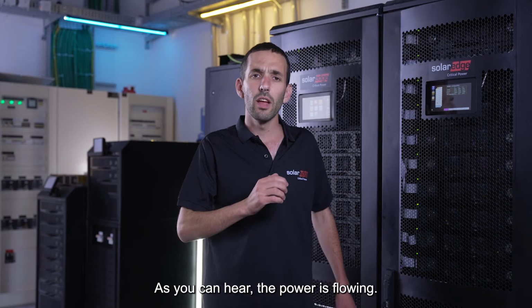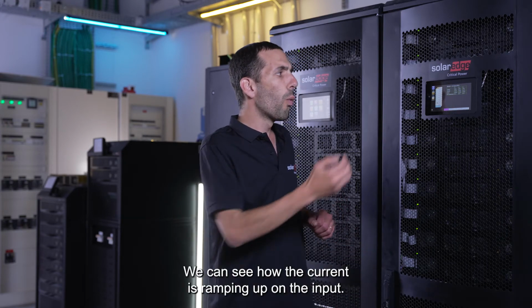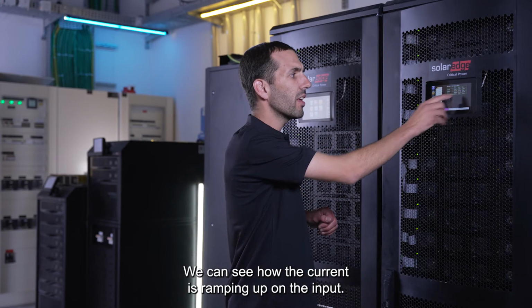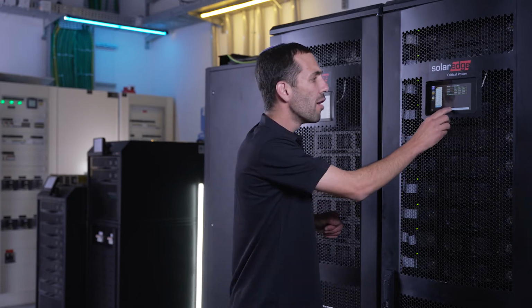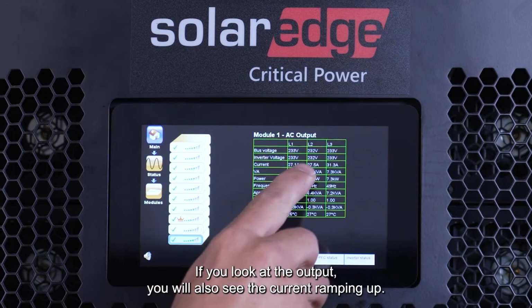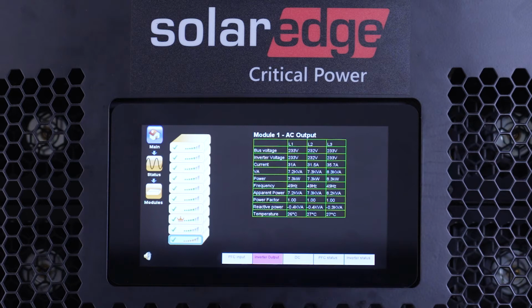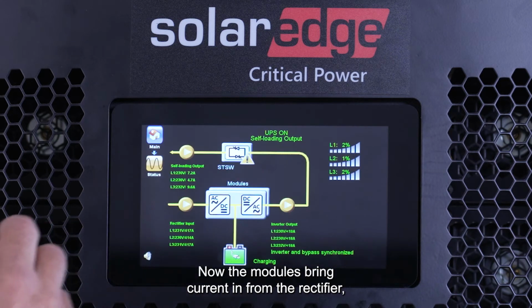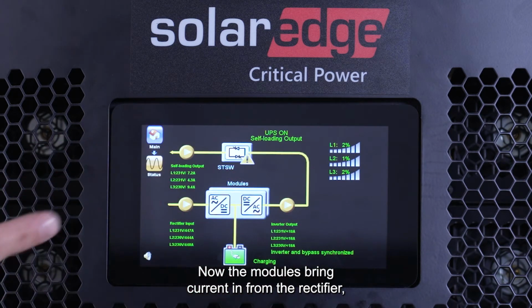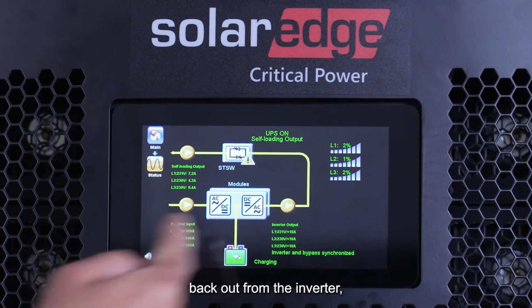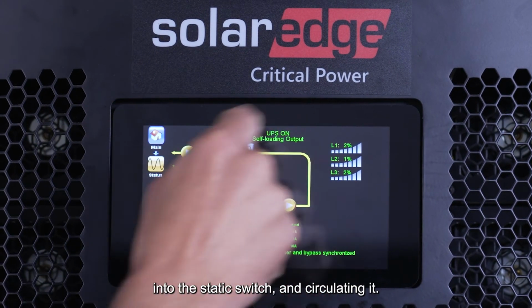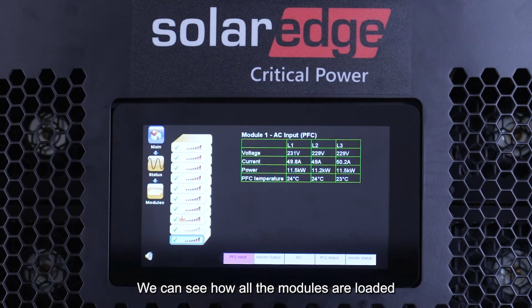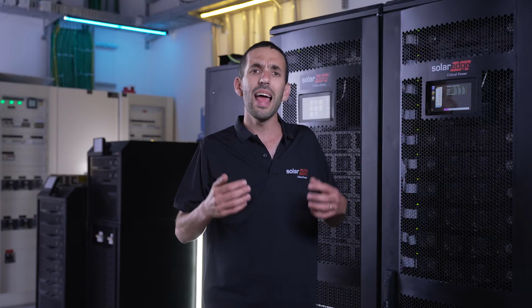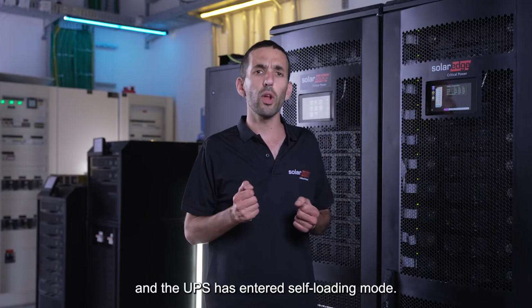As you can hear, the power is flowing. We could see how the current is ramping up on the input. If you look at the output, you will also see the current ramping up. Now, the modules bring current in from the rectifier, back out from the inverter, into the static switch, and circulating it. We could see how all the modules are loaded and the UPS is under self-loading mode.